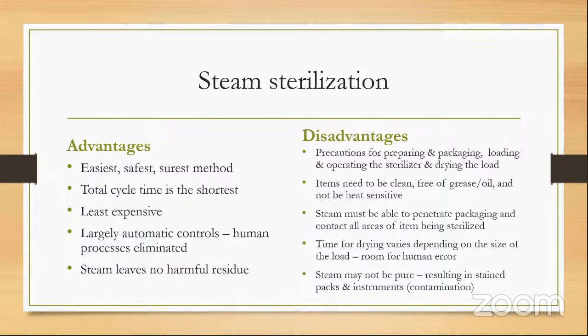Of course, the literature gives the fact that the items need to be clean and free of grease and oil and not be heat sensitive as a disadvantage. But really, when you think about it, if sterilization is what you are after, then the items really do need to be clean and free of any debris. The steam must be able to penetrate packaging and contact all areas of the item being sterilized. So this is a disadvantage in that you have to be selective about the kind of packaging that you choose for use. And the time for drying depends on the size of the load. So there's room for human error there because we can underestimate the time that is needed for a particular load to be dry.